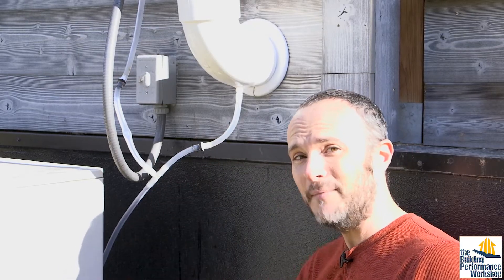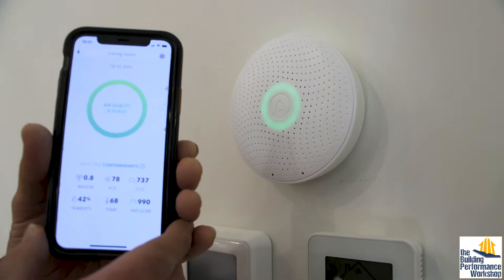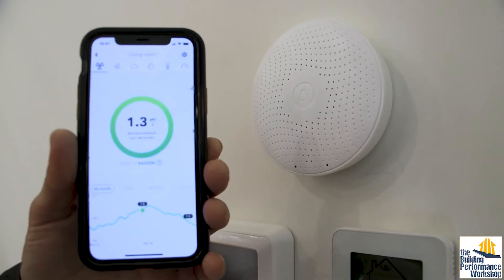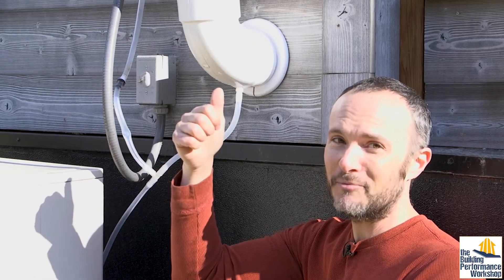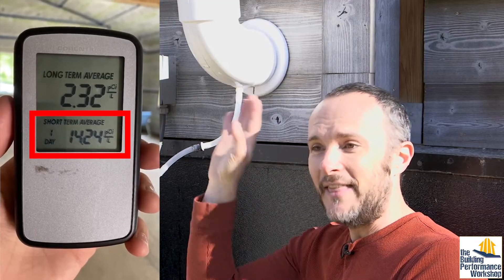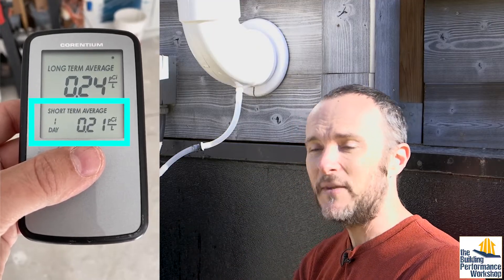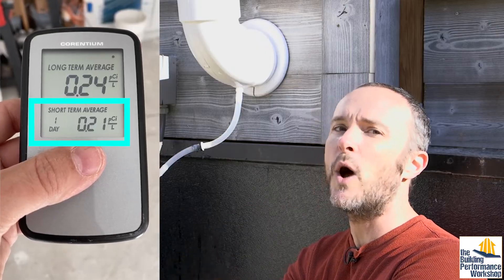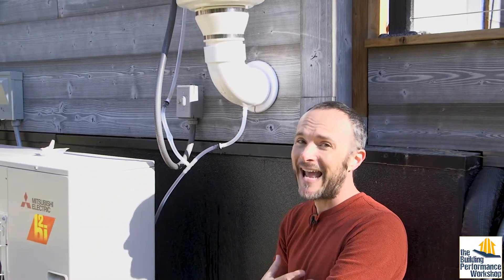This is all already working because we have the AirThings WAVE inside. The WAVE Pro is the model I've got in there, which monitors a bunch of other stuff aside from just radon. The radon level we measured before we activated the active radon system — back when it was just a passive radon system, just a pipe that goes up through the roof — did not work for us. We had extremely elevated levels of radon after the house was made so airtight. Then we kicked on the radon fan and tuned it to the right level, and now I have the same level of radon in the house as exists in the atmosphere around, which is generally less than one picocurie per liter of air. You want it to be less than four if you're following the standard, but as a dad I want it to be whatever it is outside, which is close to zero.